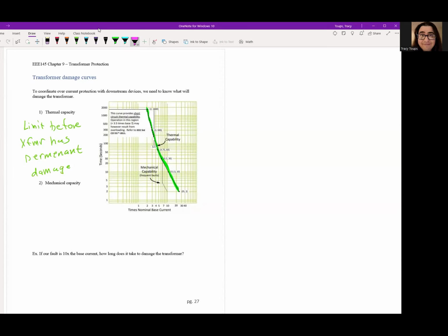There is another curve called mechanical capability, called frequent faults. It's kind of this one right here. Like so. Oh, let's try to make it a little bit better. Like that. And you can see it's a little bit lower and it stems off the main one. This is called a kind of temporary fault line where you're going to do partial damage to the transformer. Now I say partial damage because it will still work, but you put some mechanical stress on it, some heat stress, maybe some windings, the insulation might start cracking earlier. So at the end of the day, you shorten the lifespan.